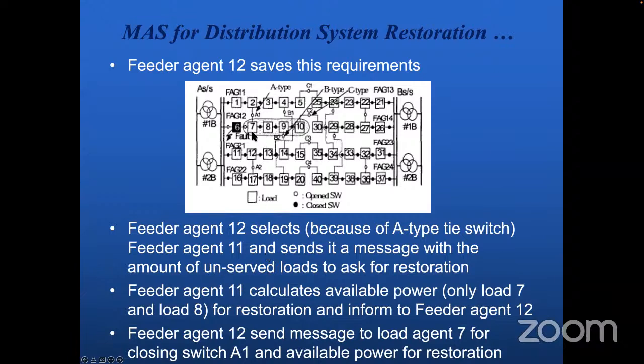How do they know the unserved load? Because these agents are measuring what the load was before the outage or fault, how much was being consumed. So feeder agent 11 calculates the available power, which can only serve load 7 and load 8, whatever the reason is.